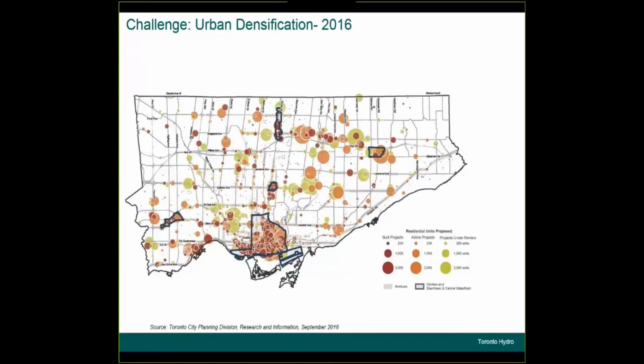Notwithstanding that, we still didn't have enough space, so with the reconstruction of the machine shop, we established that we would occupy the machine shop for our station service equipment and for our protection and control equipment, and the protection and control equipment of Hydro One. So approximately 60% of the machine shop is occupied by electrical equipment.